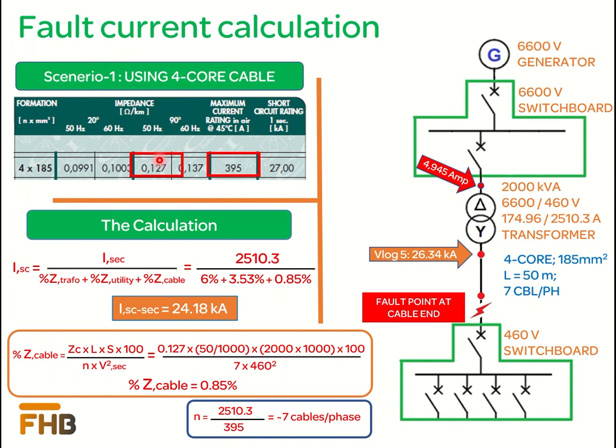L is the length of cable. Here we assume that the length of the cable between the transformer terminal and the other side of the cable connection at the LV switchboard is 50 meters. Since the cable impedance is in ohm per kilometer, therefore we need to convert the cable length into kilometer as well.